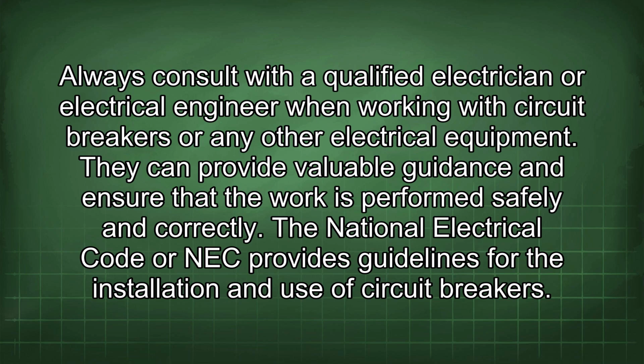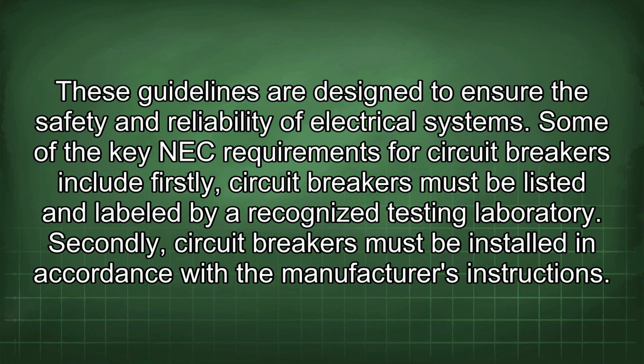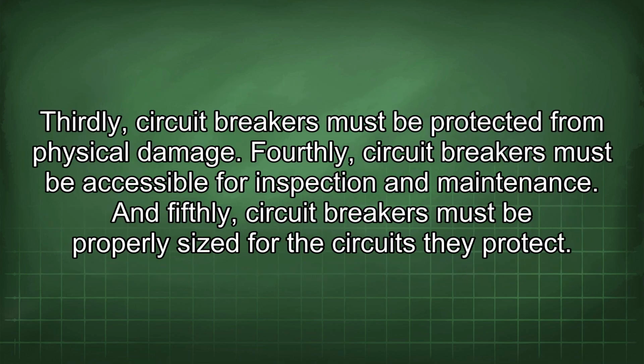The National Electrical Code, or NEC, provides guidelines for the installation and use of circuit breakers. These guidelines are designed to ensure the safety and reliability of electrical systems. Some of the key NEC requirements for circuit breakers include: firstly, circuit breakers must be listed and labeled by a recognized testing laboratory. Secondly, circuit breakers must be installed in accordance with the manufacturer's instructions. Thirdly, circuit breakers must be protected from physical damage. Fourthly, circuit breakers must be accessible for inspection and maintenance. And fifthly, circuit breakers must be properly sized for the circuits they protect.